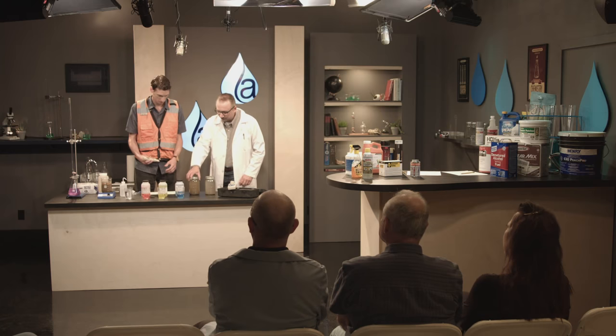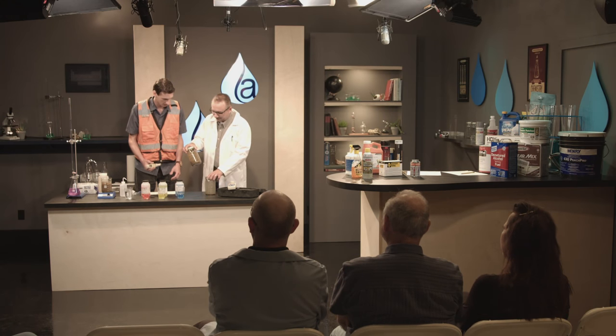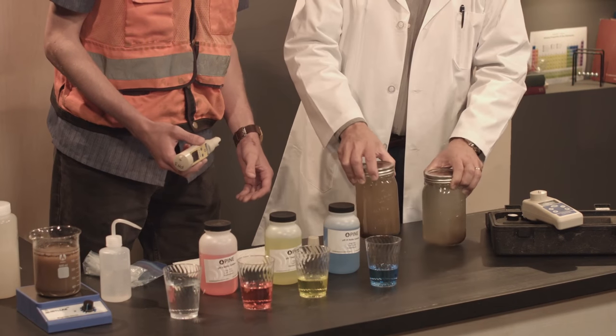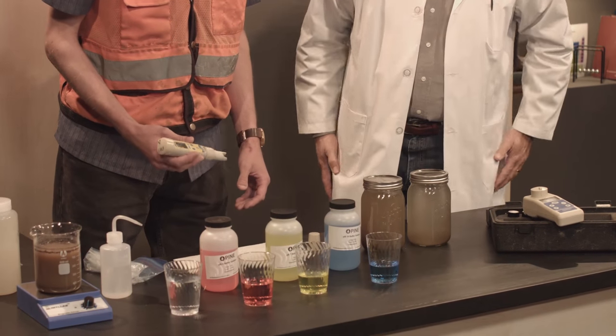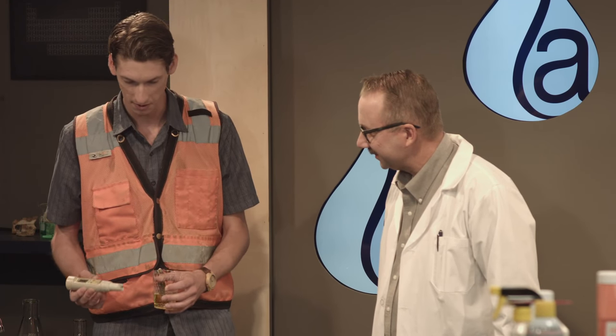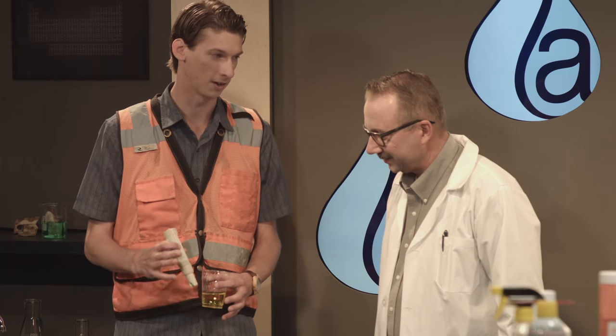We have two samples here. The first thing you want to do is rinse off the pen — you don't know who used it last. I've found that if you go from a site with high pH and don't rinse your pen, then go to another sample location that might be low, you could still have residual on there. You have three standards: high, middle, and low — 10, 7, and 4.